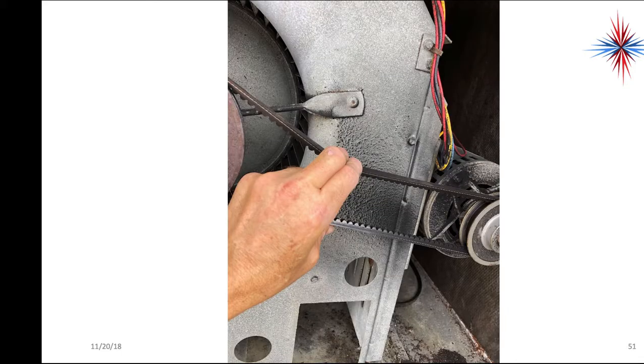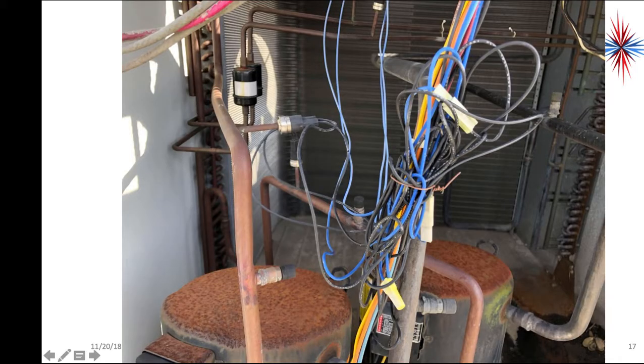Now, back to earlier in the presentation, I had talked about a ball of wire here. I did find out why the compressor failed. Let's get back to my ball of wire right there. I pulled this wiring apart and I traced our pressure switches. Ideally, that low pressure switch on the refrigeration circuit would have taken the compressor out of the circuit and actually opened, making sure that compressor was protected and was not going to run dry.